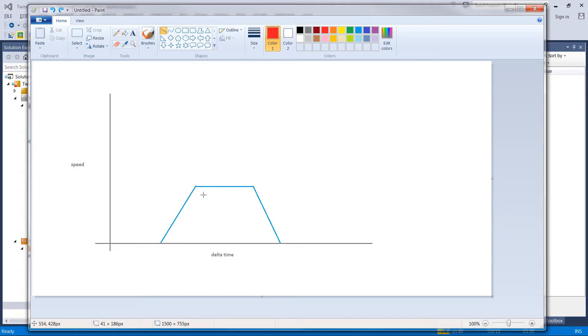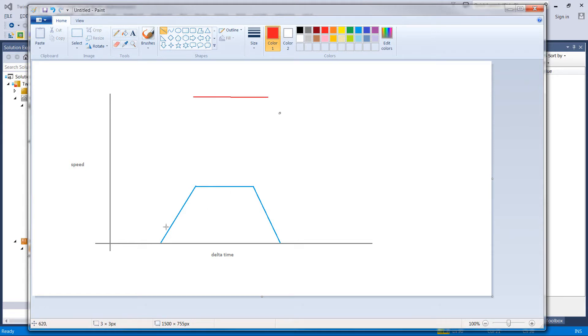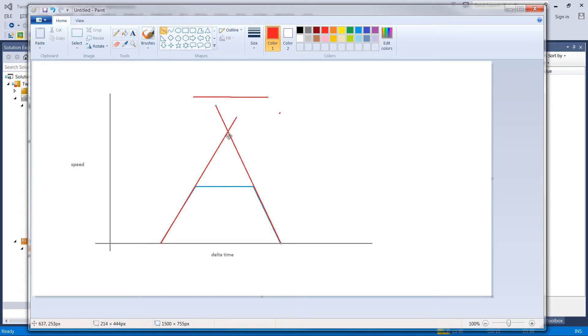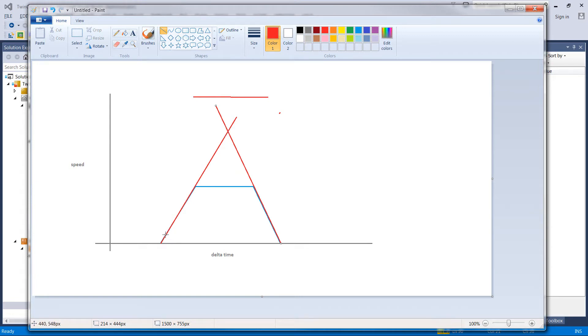So this is your acceleration number. This is your Vmax number. If you manage to put Vmax so high, so say Vmax is way up here, and your accel looks like this, and your decel looks like this, the point that they cross is sort of an artificial Vmax, and that's what I call a triangular move, which is perfectly acceptable. That's kind of the highest performance move that you can do for a given acceleration and deceleration. So if you're really trying to get cycle time out of it, you want almost a triangular move. So as soon as he's done accelerating, he begins decelerating.